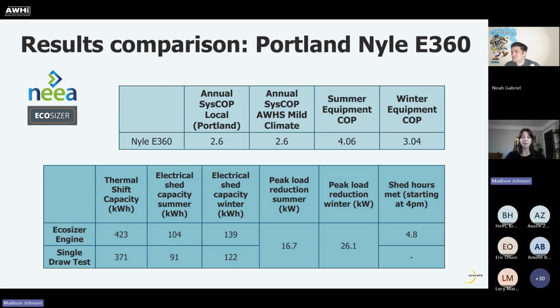This top table shows performance data from the product assessment data sheet. The E360 is expected to have an annual system COP of 2.6 in Portland, and an equipment COP of about 4 in summer and 3 in winter. The bottom table shows results from our two methods for quantifying load shift capacity. This building is quite large, so it translates to a large primary storage volume and large thermal shift capacity.